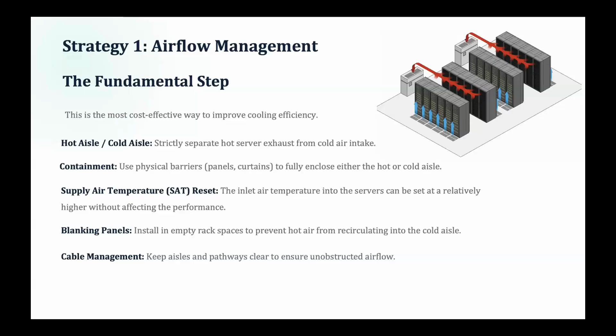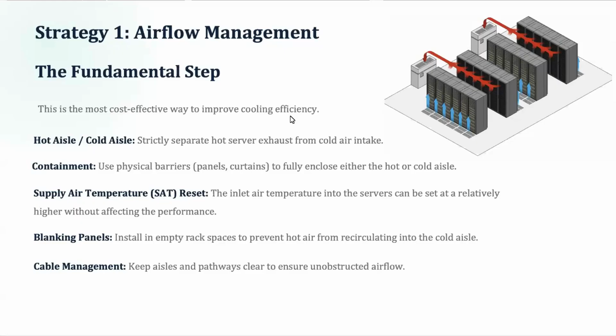Now, cable management. Most of the cooling presently is still supplied to the servers using raised floors, where the conditioned air from the unit is supplied through the underfloor panels, and some panels are kept open at the server entrance level to get the supply air inside to the servers. Now, if that path is blocked by cables or any other materials, a vortex will be created inside that supply air stream, and that will affect the supply air movement across the server racks. So it is always better to have the cables confined to the floor, such that the supply air stream is not affected in any way.